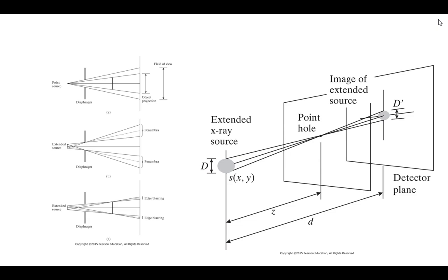What's the disadvantage of doing that? Life is a trade-off, right? Less intensity. And the lowered intensity means I've got to get a more concentrated beam off of them. Ideally, I'd like a more concentrated source beam from it, so I don't just have to throw away a lot of those other x-rays and waste energy, and effectively life and heat and things on there. So source distance is another thing I can control, with trade-offs. What else can I do?